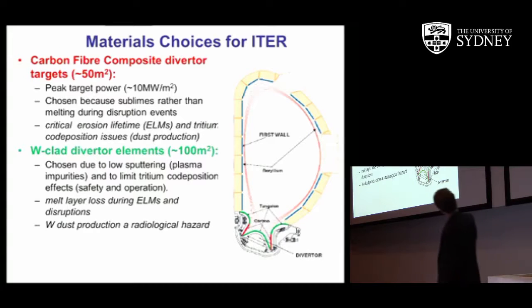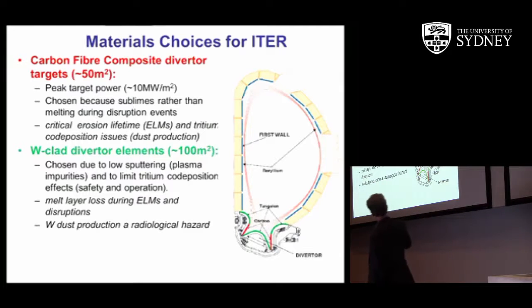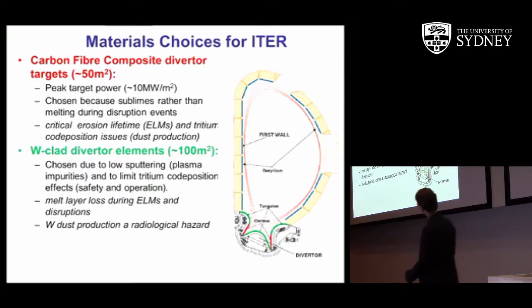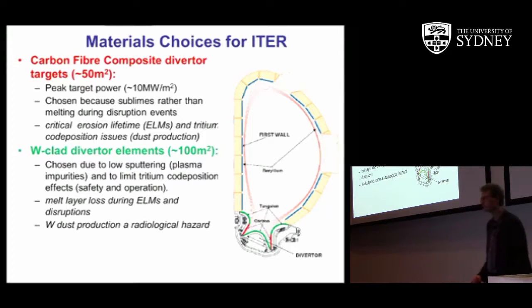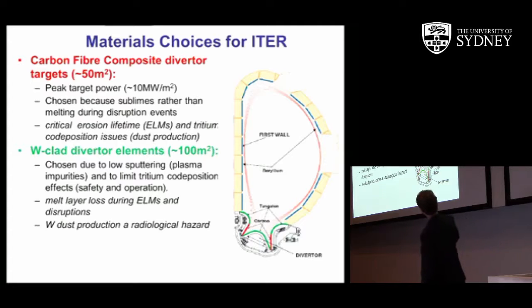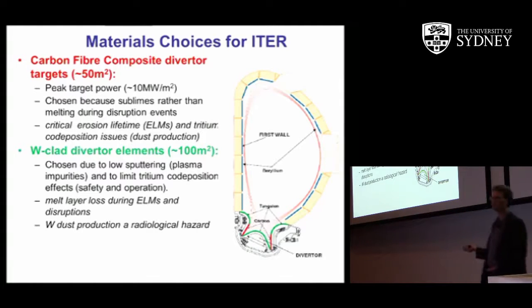Elsewhere, the machine is clad in tungsten, and the reason why you would choose this is because it has low sputtering and limits tritium co-deposition. So the problem with carbon is that it has a tritium co-deposition problem. It absorbs tritium, and then you have tritium dust accumulating inside the machine, which is a radiological hazard.